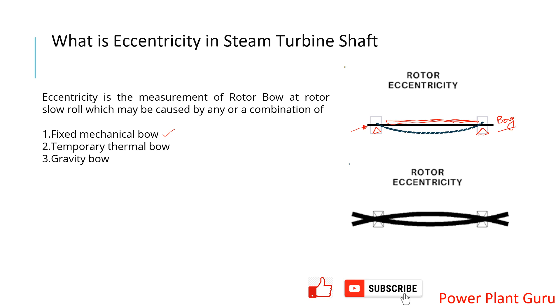There are also temporary thermal bows. In case of uneven heating or uneven cooling of your turbine, it may give a temporary bow to the rotor, which can be equalized by running the machine on slow speed — which is called barring — and it will definitely normalize. And the last type is the gravity bow: if you keep your rotor at standstill, at 0 RPM, for a long time, then the rotor will definitely have a tendency to bow — like a banana shape. That is why you will see a bow in a steam turbine when it is coming from a large shutdown or outage.